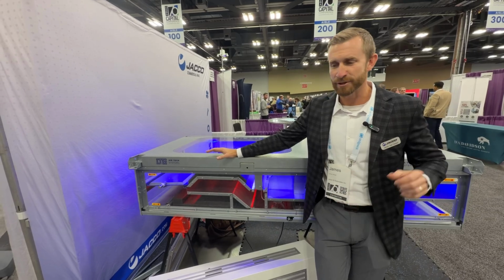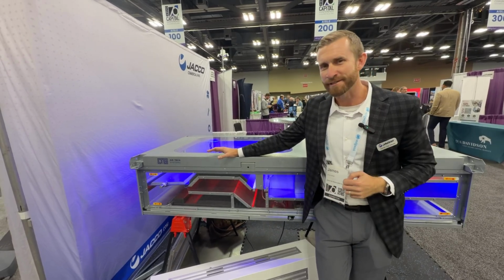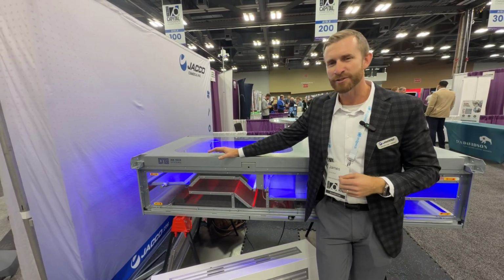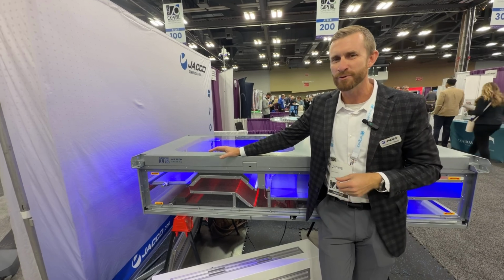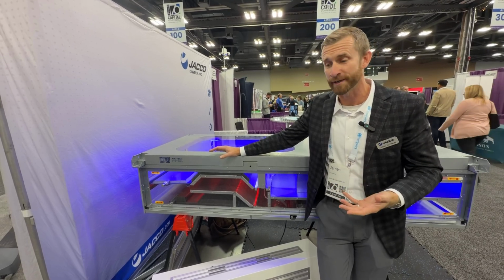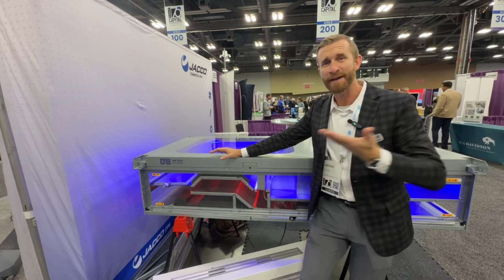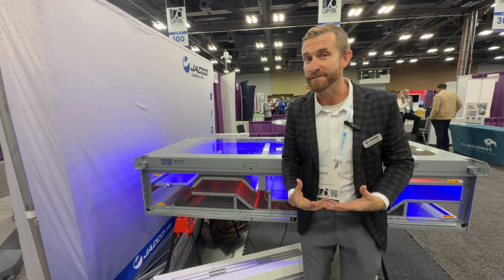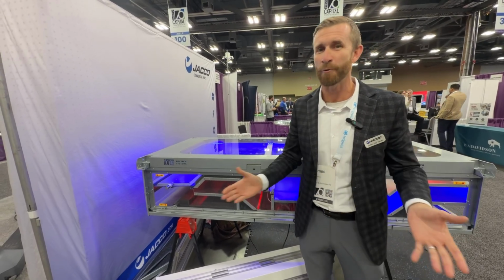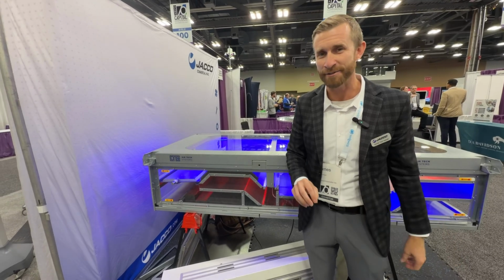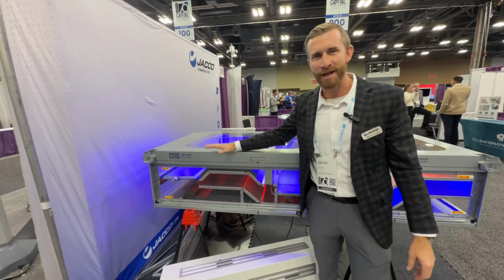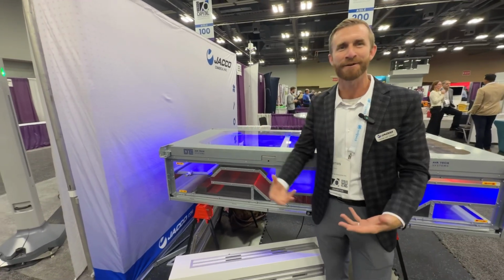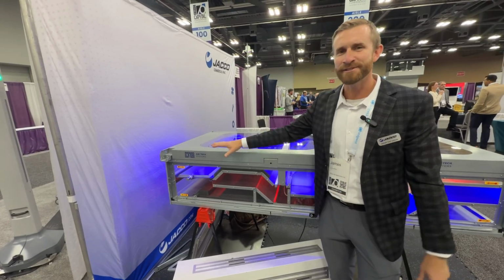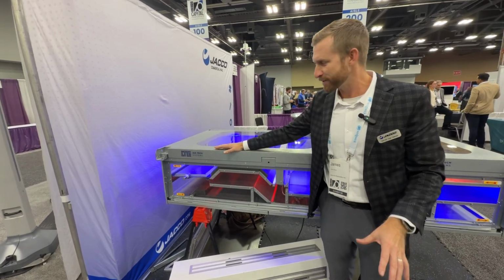The other side of that is if you're just bringing it in, 360 CFM is going to take roughly 2.2 to 2.25 tons of heating or cooling to bring it from 0 degrees back up to 68. 2 tons. Your home system is probably only 4 tons total for your entire house. So if you think about that, every classroom is going to need 2 tons to bring in the 360 CFM. This solves both of those problems, and let me show you how.